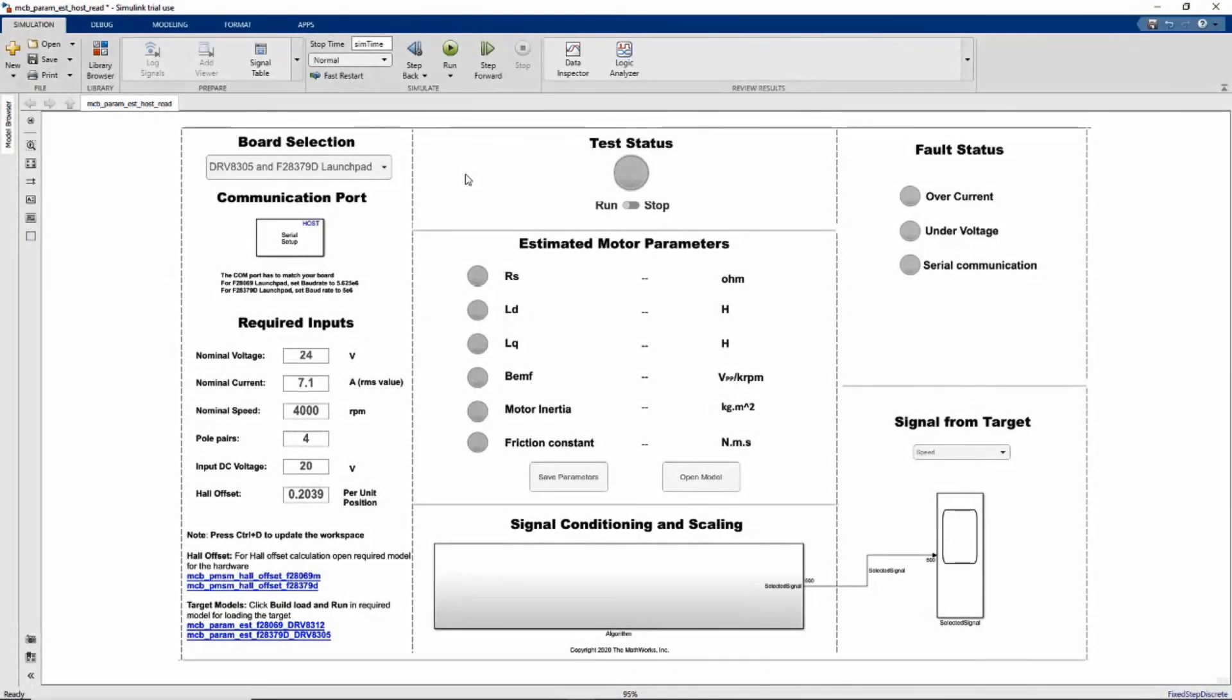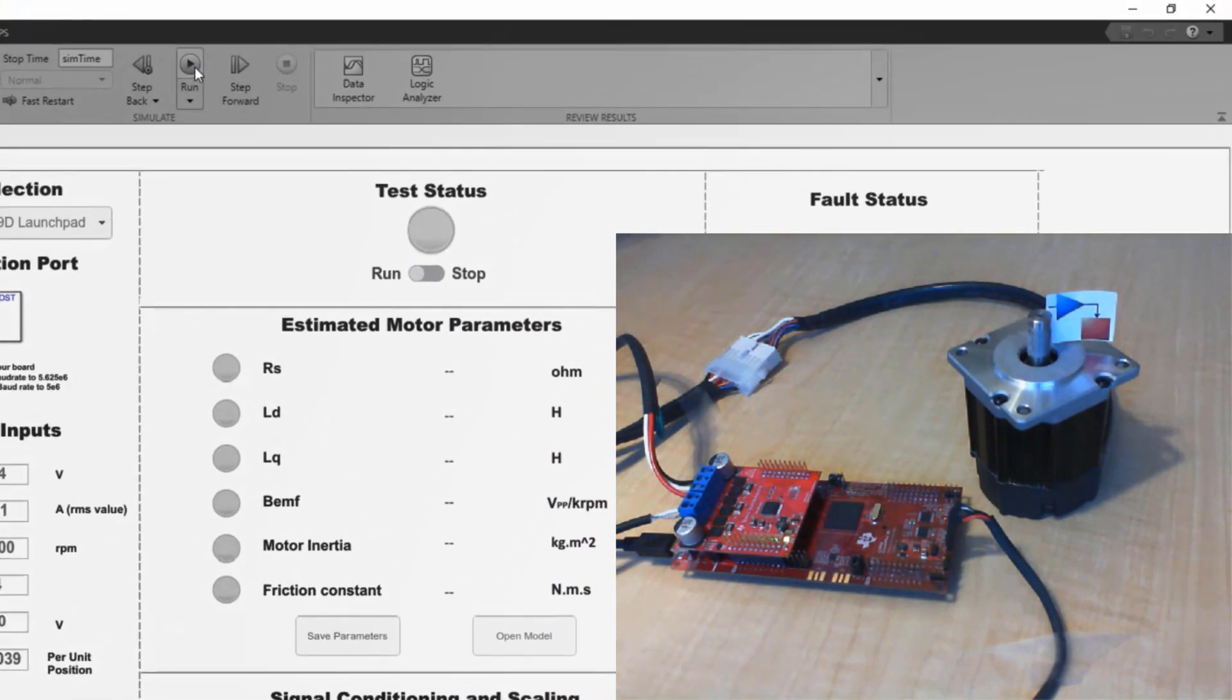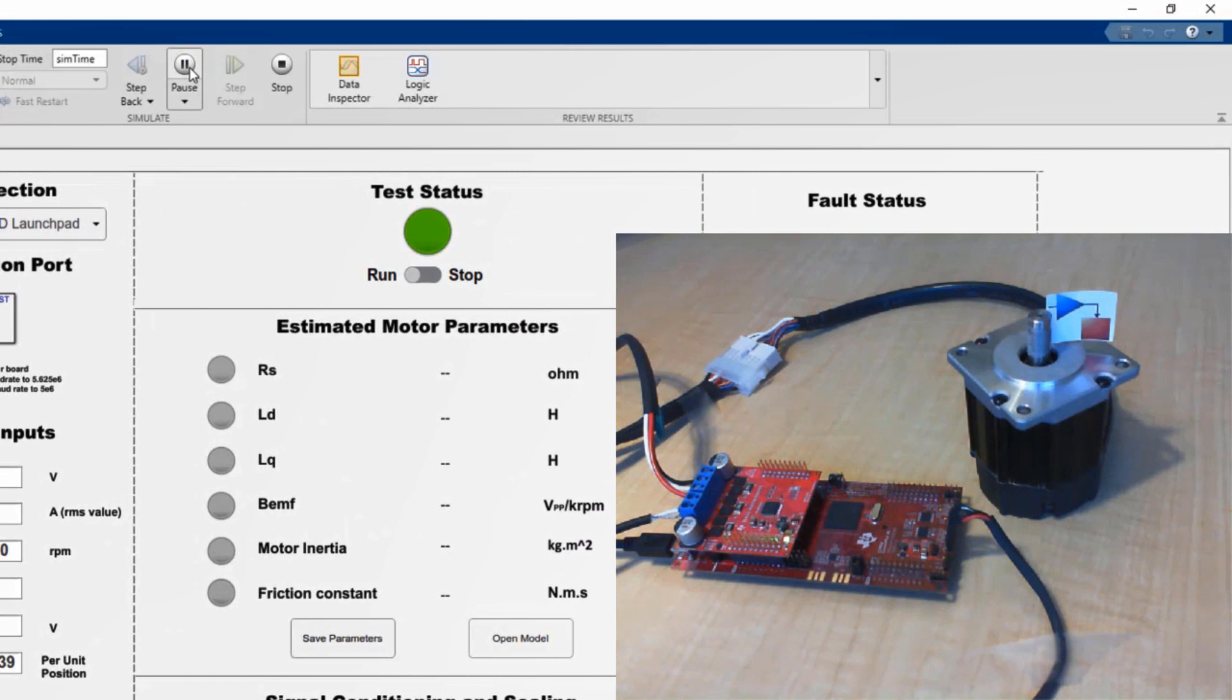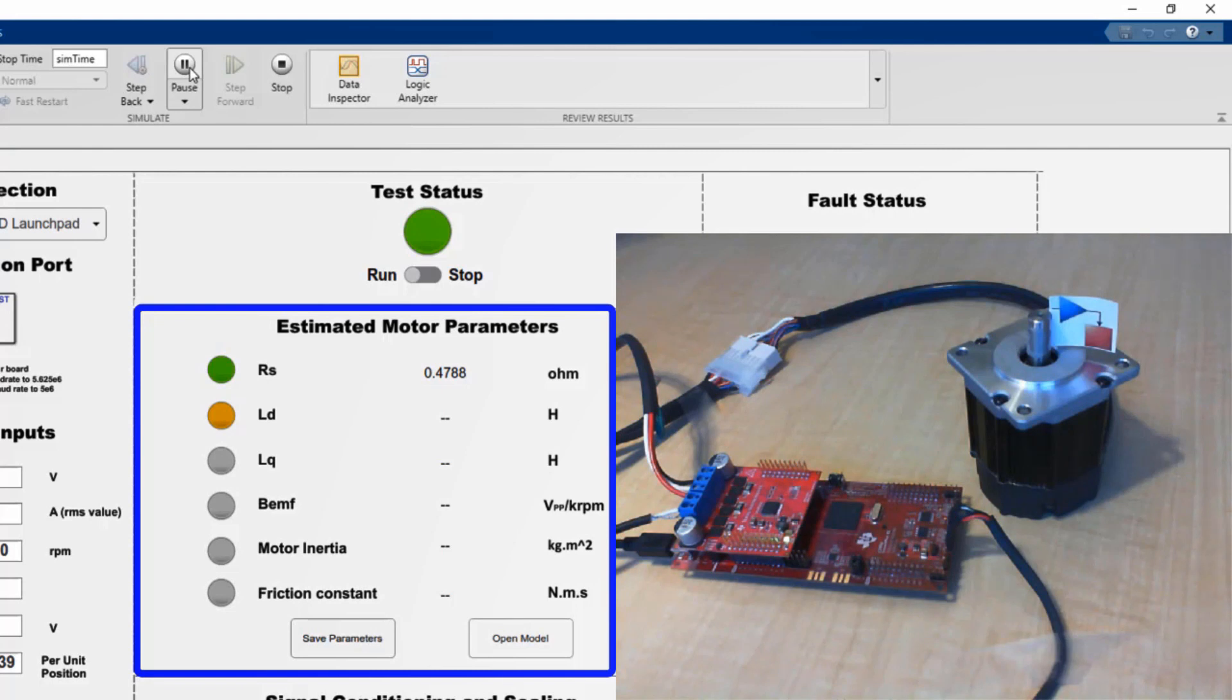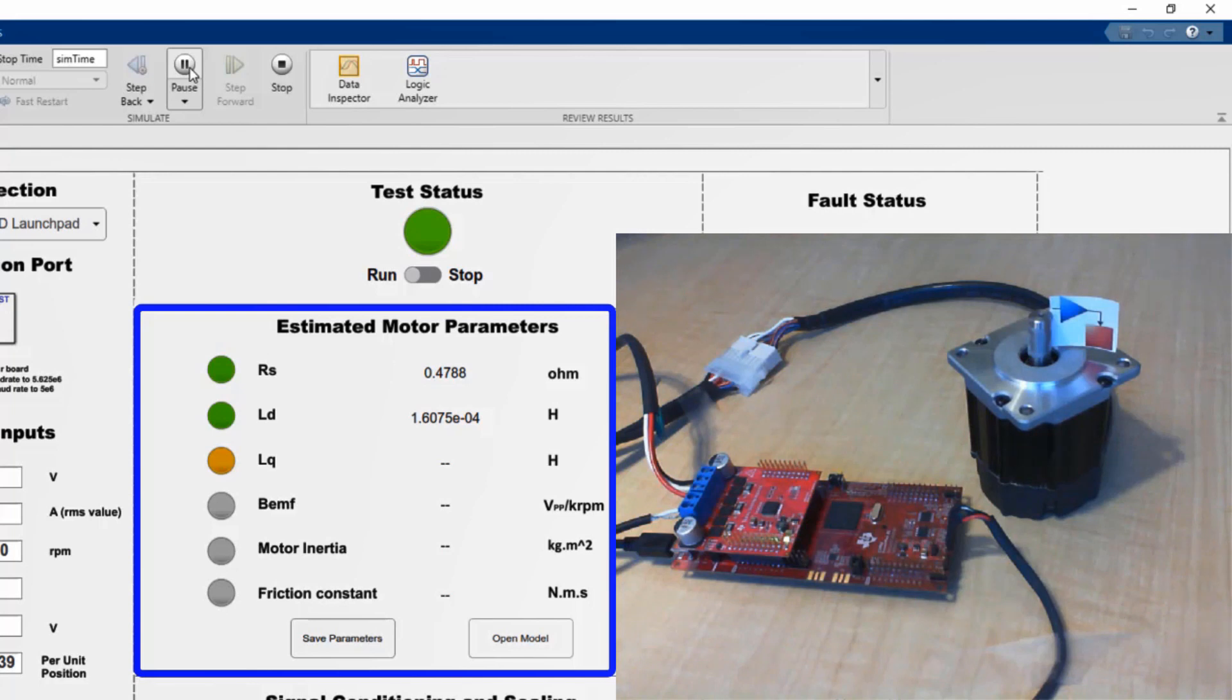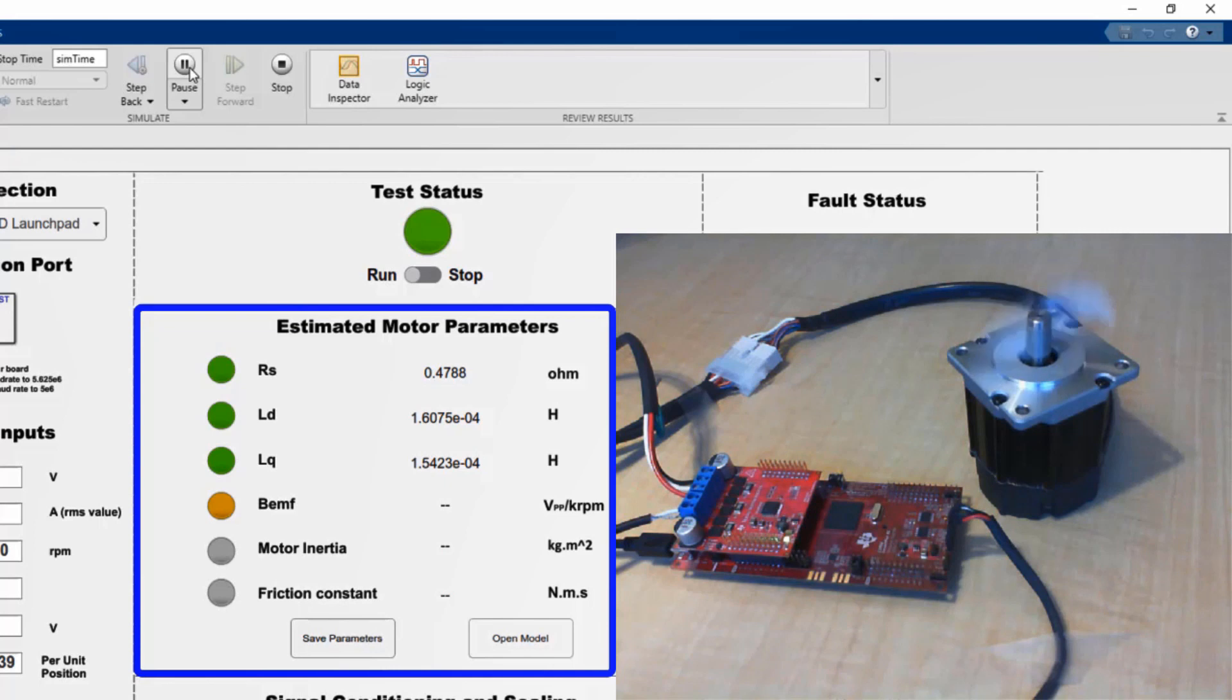We then start parameter estimation from the host model. Tests are run on the motor to estimate stator resistance, inductance Ld and Lq, back EMF constant, moment of inertia, and friction coefficient. So it's going to take around 30 seconds to finish the estimation process.